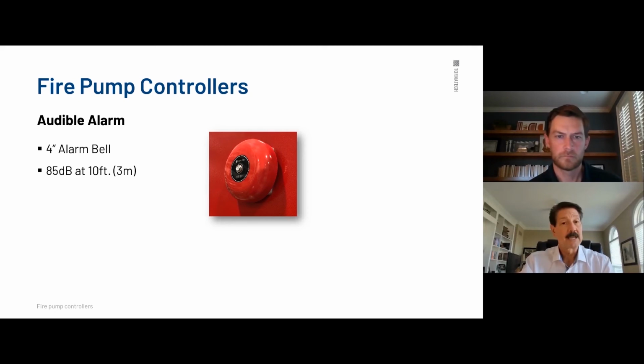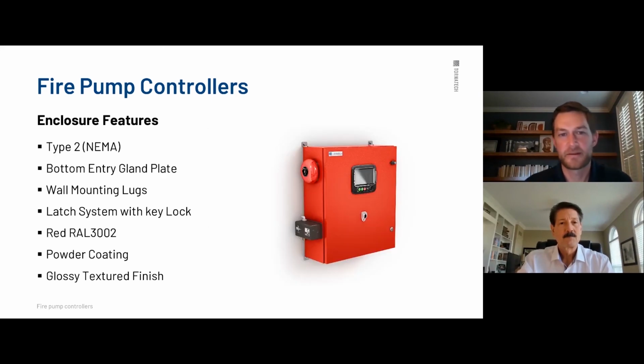We still have the same retro bell, about 85, 90 dB. I mean, obviously, when I was growing up, we heard a bell, it was fire alarm, or it was lunchtime. So it's that kind of a bell. Enclosure, NEMA 2, drip proof. You can see the alarm here. Externally mounted wetted parts, which is our pressure connection in here for our half-inch sensing line. It's a NEMA 2. As I mentioned, it's lockable. Latch and a lock up here.